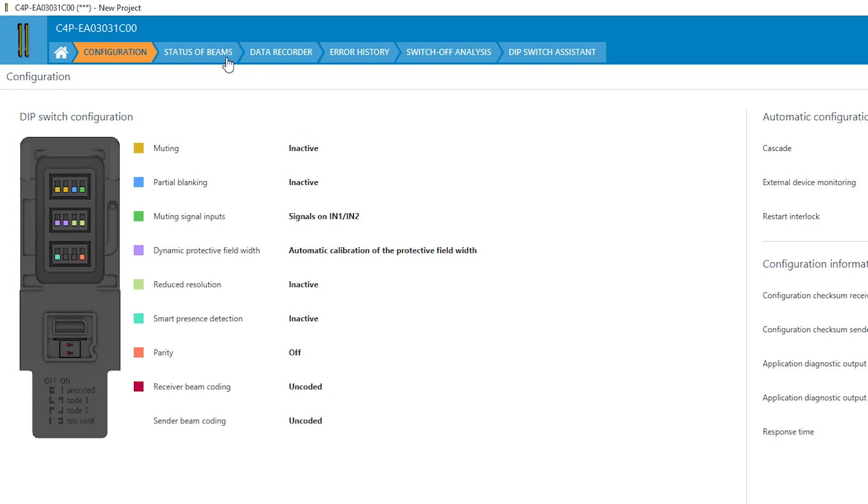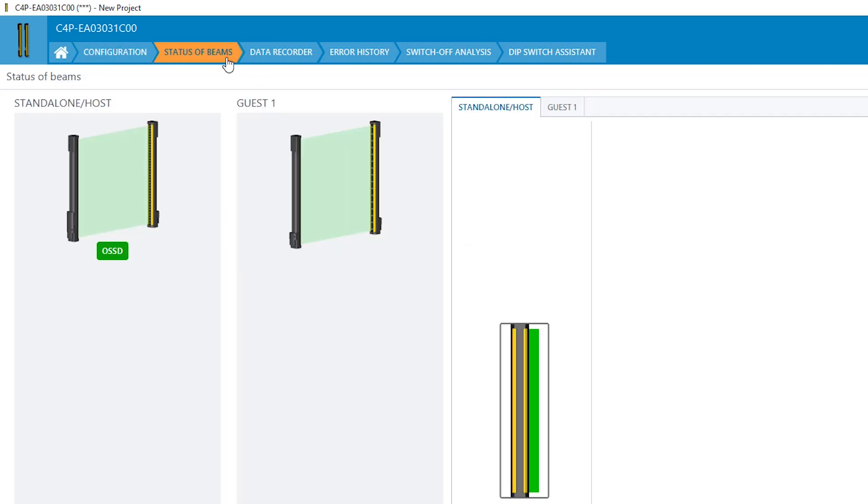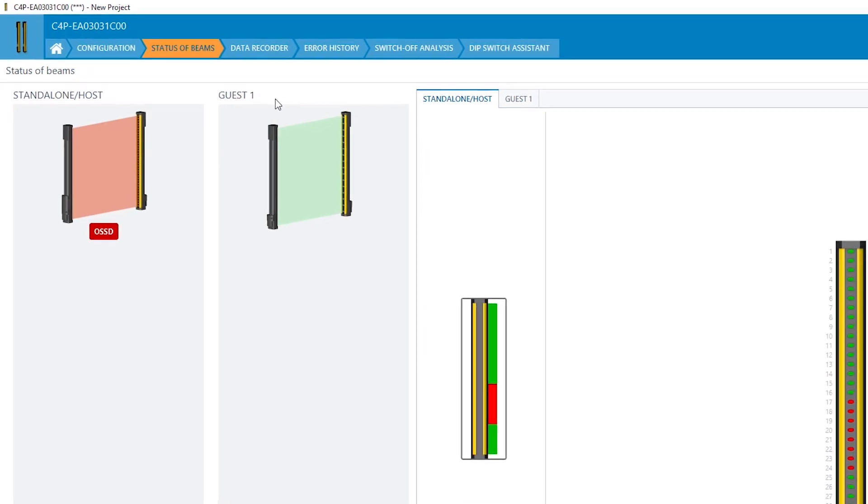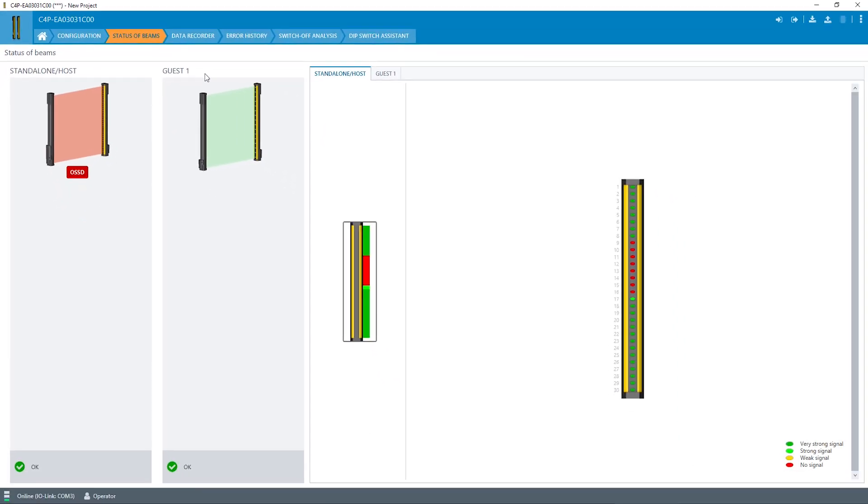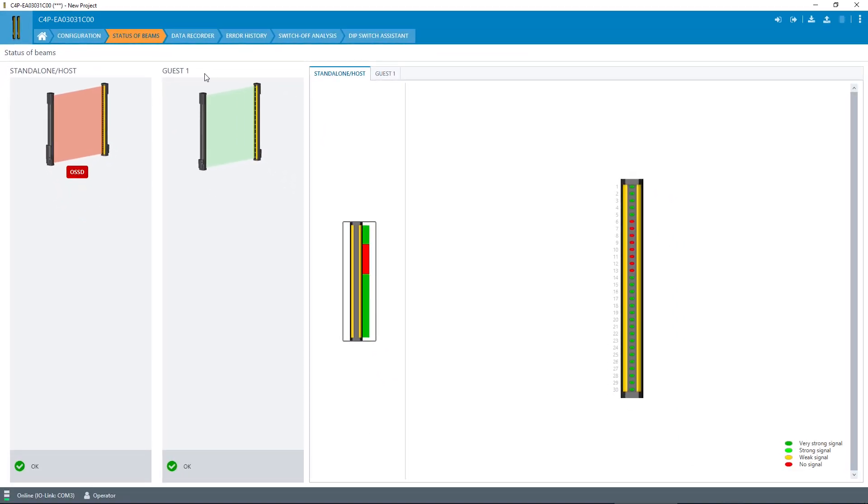The status of every single beam of the DTEK4, either in a standalone system or in a cascade, can be viewed in the tab status of beams. This can be useful during the commissioning of the system and its alignment. It also shows you whether the device has to be cleaned or realigned.